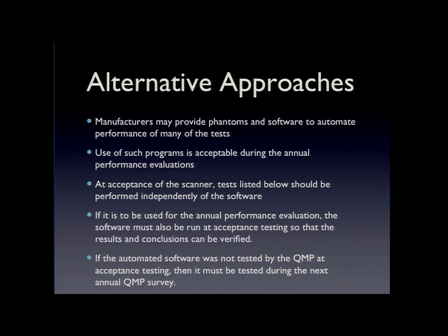As I said, with the alternative approaches, even though we use the ACR accreditation program, you can use the manufacturer's phantom. You don't have to use the ACR phantom. But if you use it, you have to use their method. You can't use their phantom and then use a different method to do it.